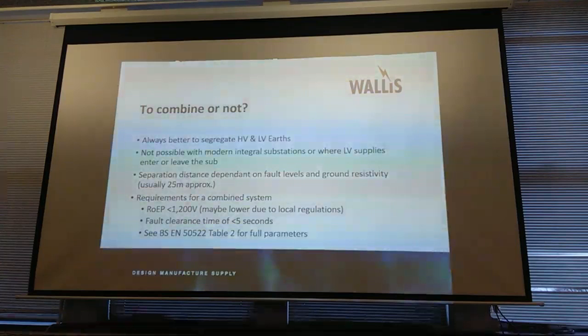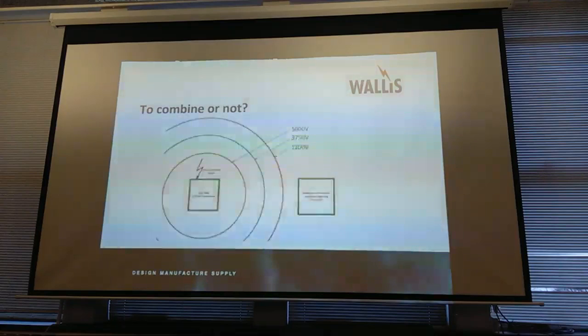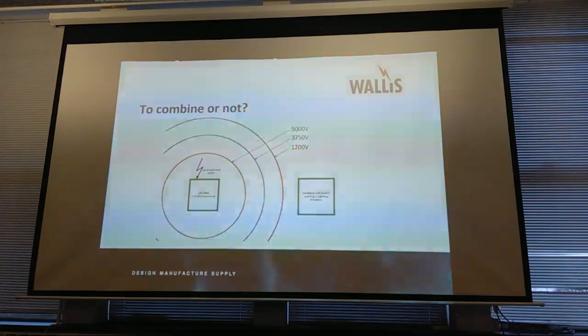There are other instances where if you've got telecoms in the building, you might have to look at a lower value, because S34 then talks about 430 volts contours. Openreach, Virgin Media and people like that, where they're bringing copper pairs into your building, they don't want that sort of level getting onto their 50 volt telecom systems. So again, you're not just looking at one value, you've got to look at 1200 volts, 430 volts, different values. Yeah, that's all. That's the part past on that.